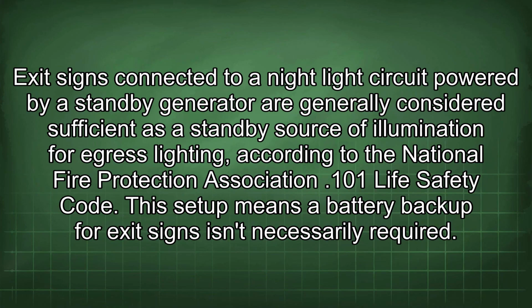Exit signs connected to a night light circuit powered by a standby generator are generally considered sufficient as a standby source of illumination for egress lighting, according to the National Fire Protection Association 101 Life Safety Code. The setup means a battery backup for exit signs isn't necessarily required.